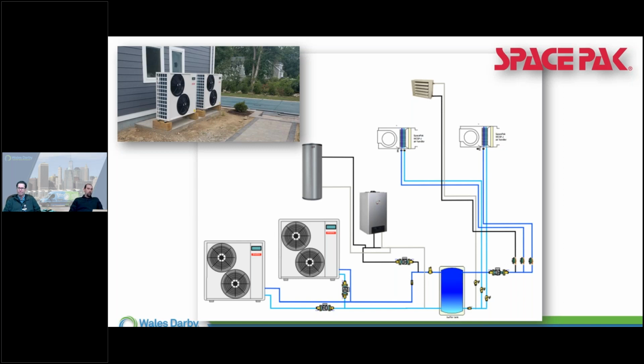Not to get too much deeper, but you mentioned snow and ice and being air source. That's one thing with air to water: you don't really have to worry too much about defrost because you don't see it. It's not like air to refrigerant, or air to air, I should say. When that thing goes into defrost, you reverse the cycle of the machine, and now you're taking heat away from the space for a limited amount of time. The technology's gotten pretty good there, and defrost times are getting a lot shorter. But with air to water, when that thing goes into defrost, all that outdoor unit cares about is that buffer tank, if you remember. So we're still pumping heat out of that tank into the home. We're not seeing the effects of defrost in the house, but you still want to make sure that thing is clear. So I just wanted to make that point.